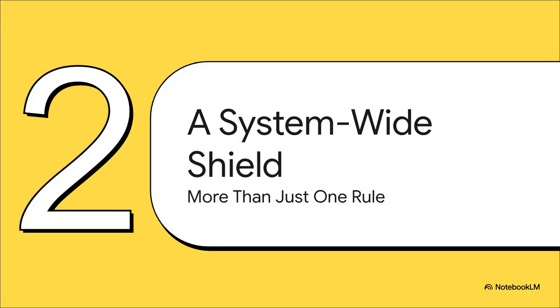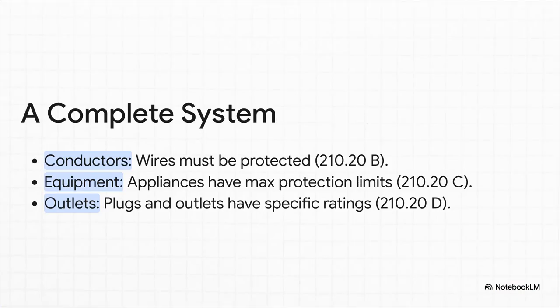And what's really cool is that this rule doesn't just exist in a vacuum. True electrical safety comes from a layered, system-wide approach. The 125% rule is just one piece of a complete shield that's designed to protect every single link in the chain. This same section of the code protects the entire system. It protects the wires running inside your walls. It protects the appliances you plug into them. It even protects the outlets themselves from getting overloaded. It's just a brilliant illustration of how every single component is thought of, creating this complete shield of protection around you.